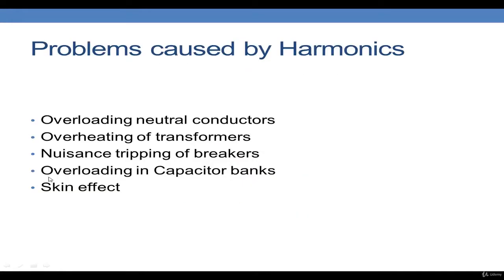One problem caused by harmonics is overloading of neutral conductors. For a balanced three-phase supply, the neutral current is essentially zero. However, in buildings with a large number of computers, PCs, and other power electronic loads, the third harmonic current gets added in the neutral conductor. As a result, the neutral conductor must be very large to accommodate these harmonic currents, otherwise it can lead to overloading and fires if the neutral conductors are not rated appropriately.